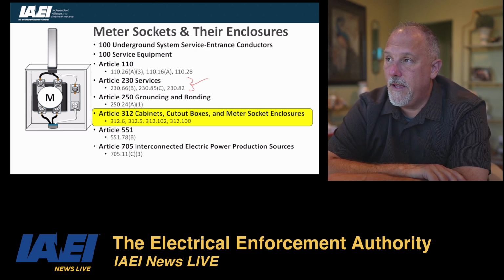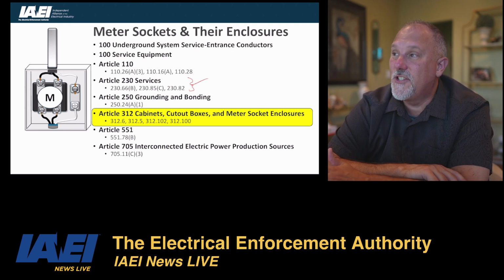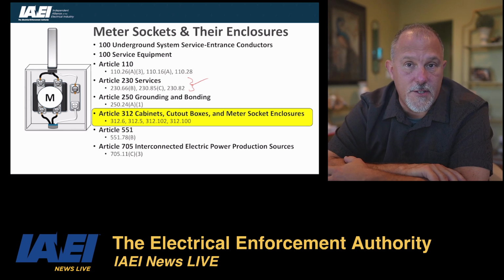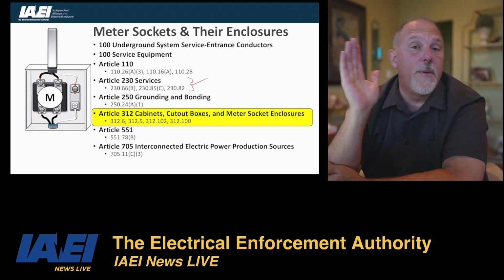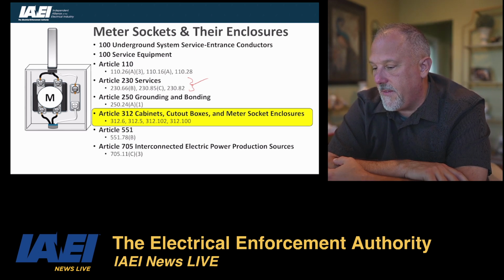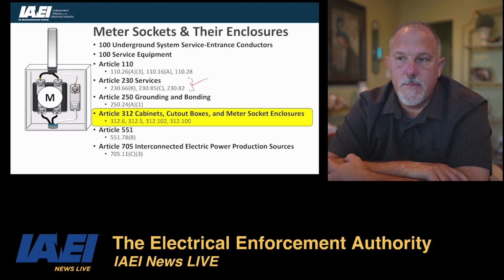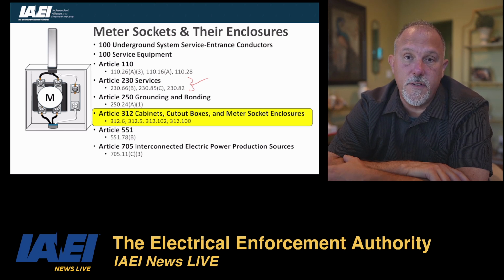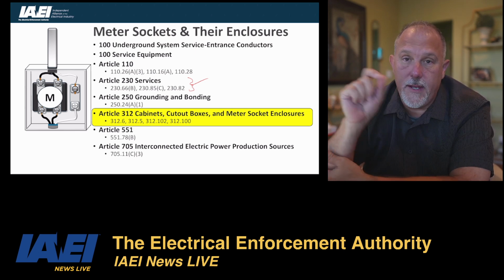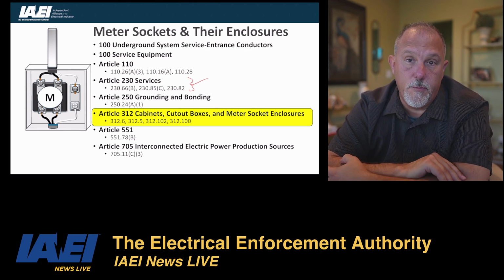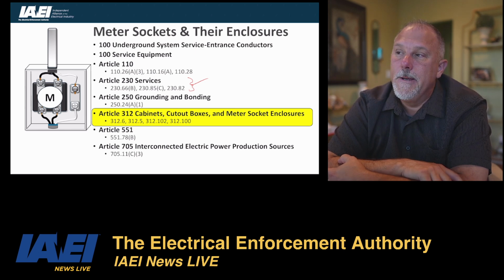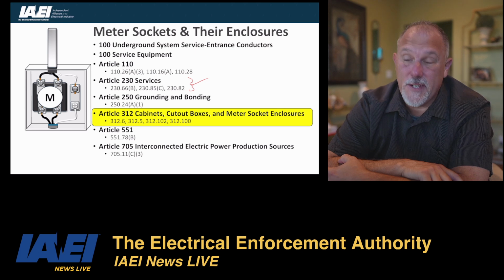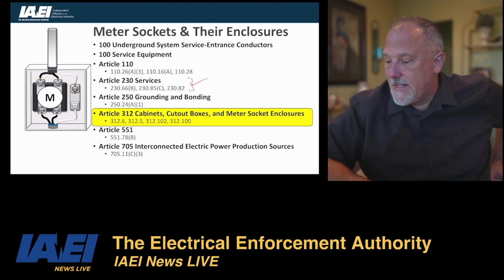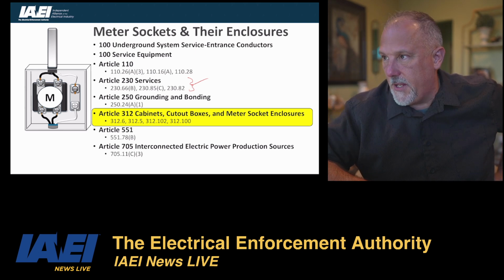Honestly, if you're changing out a meter socket, if you're changing out the service entrance conductors, I mean, that would be... I'm not sure I agree with the exception, but it's there. In the case of adding a transfer switch, you're changing equipment. You're taking what used to be the service and making it a feeder panel, and you're doing that by undoing the bond, and then adding new service equipment. So in any case, that's 230. Those are the requirements in 230.